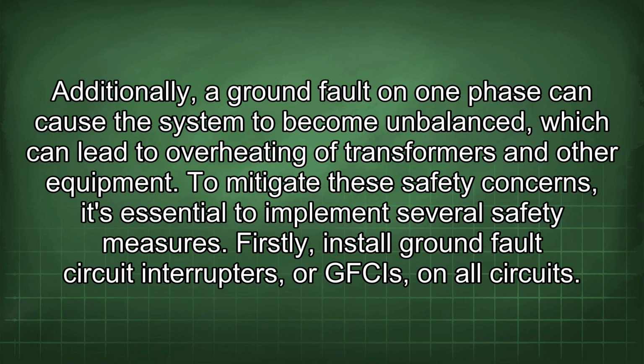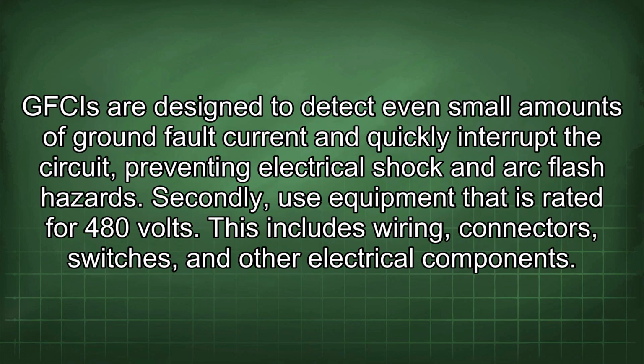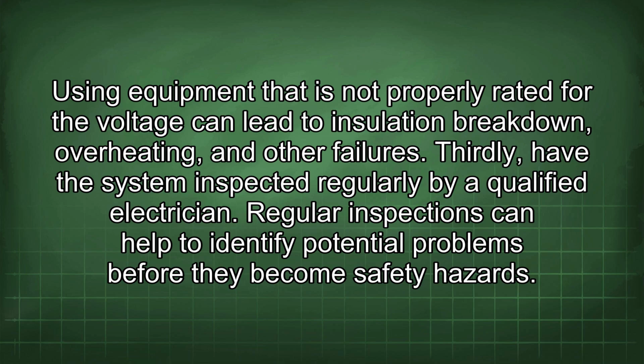Firstly, install ground fault circuit interrupters or GFCIs on all circuits. GFCIs are designed to detect even small amounts of ground fault current and quickly interrupt the circuit, preventing electrical shock and arc flash hazards. Secondly, use equipment that is rated for 480 volts. This includes wiring, connectors, switches, and other electrical components. Using equipment that is not properly rated for the voltage can lead to insulation breakdown, overheating, and other failures.